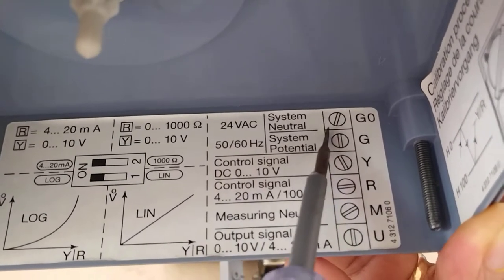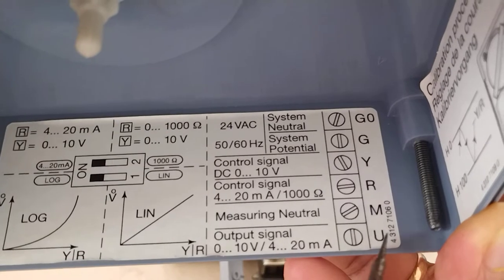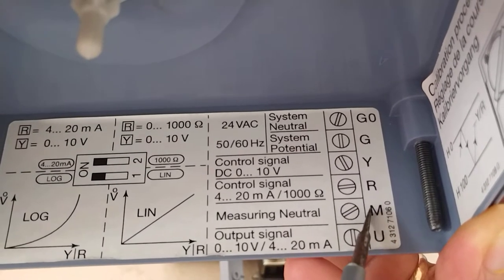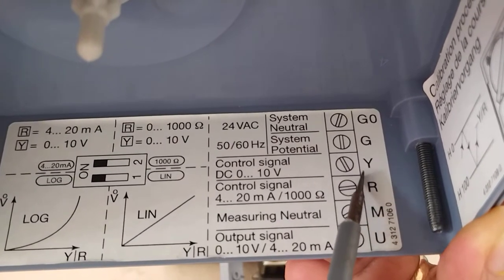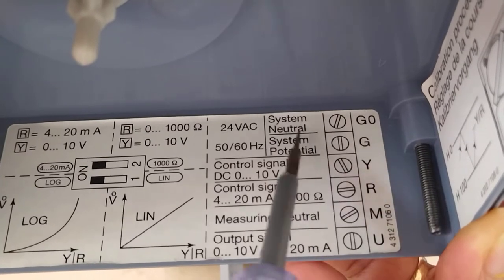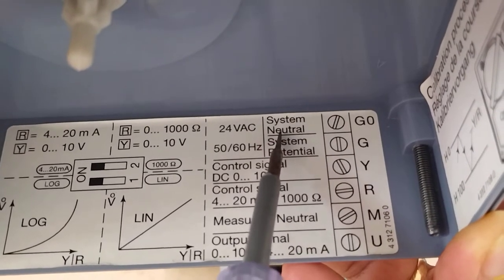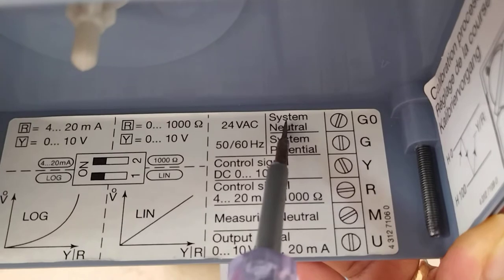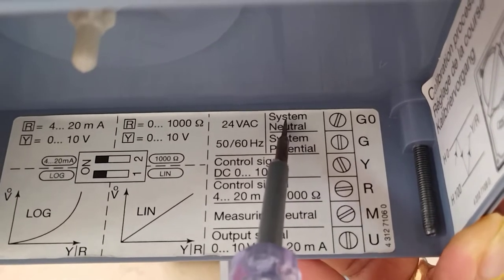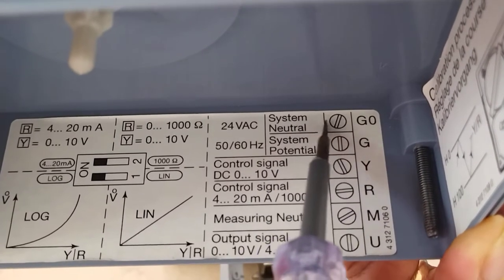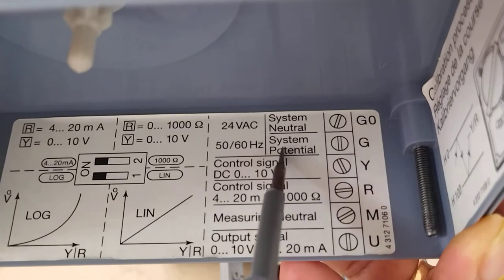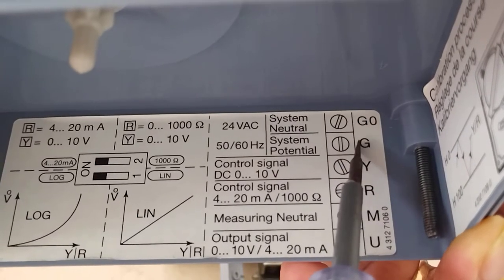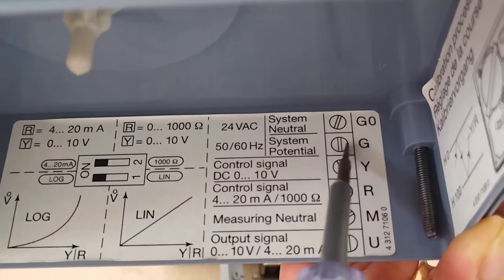Now, what are the terminals? We have U, M, R, Y, G, and G0. G0 is the system neutral. So let's say you are providing 24 volts; this is the 0 volts or neutral. Then we have the system potential, labeled G, which is the live 24 volts.